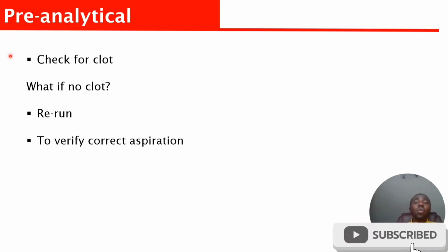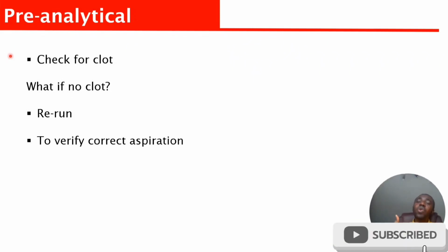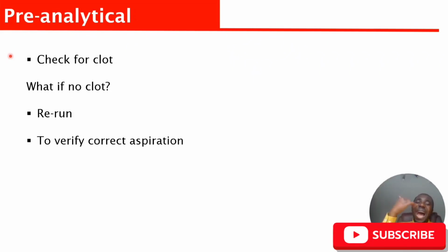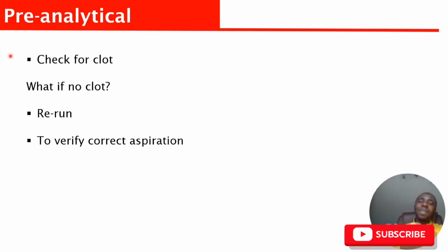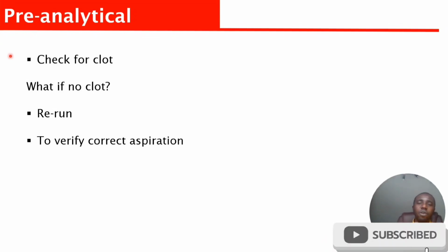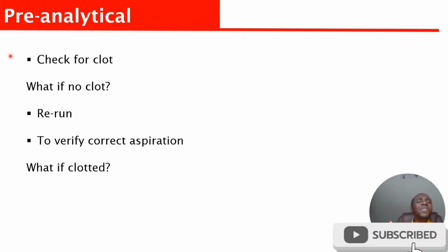So that's why you mix the sample very well, and then you can put it back in the analyzer and rerun the test. You are rerunning it so that you can confirm that the analyzer has taken enough volume the first time.